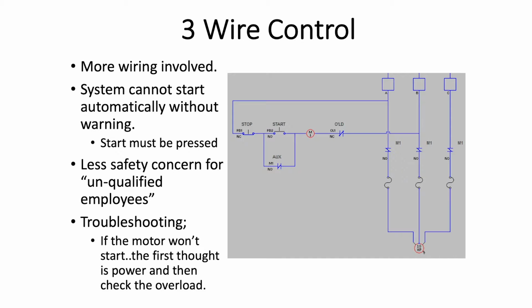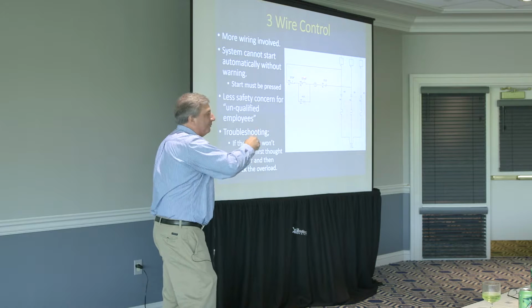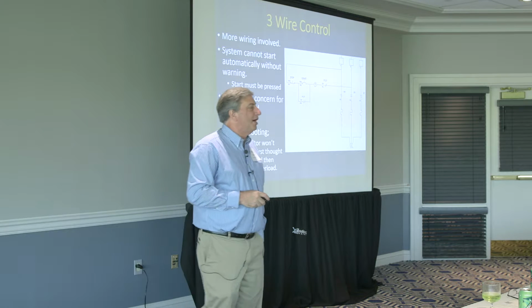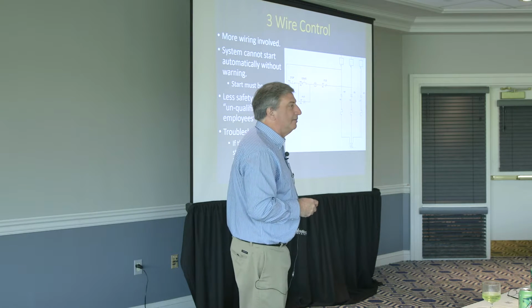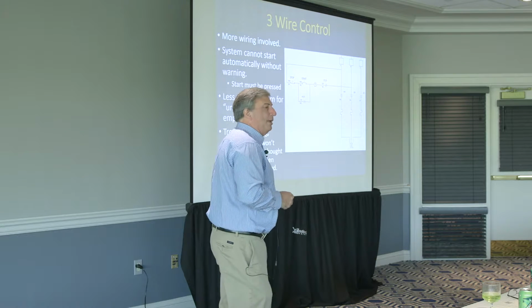If you look at a ladder diagram or a wiring diagram of what's going on with 3-wire control, it makes perfect sense, because if that starter is de-energized because the overload tripped out, then to get that starter and that motor down here back on, I have to push the stop button or start button to get it back on. Okay? Why don't people like that?